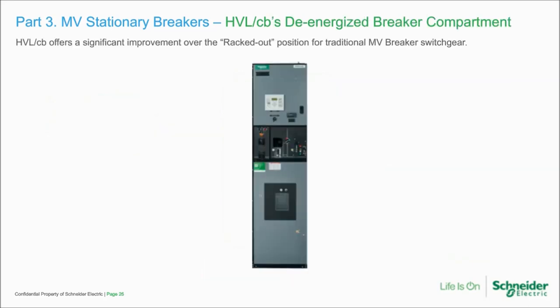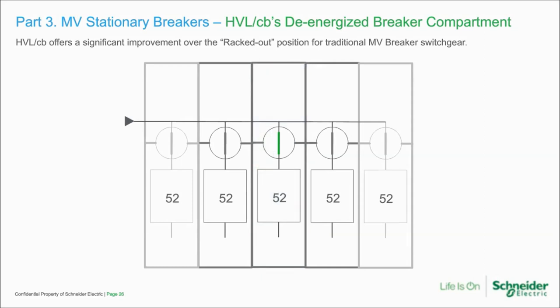This is a great improvement over the racked out position of traditional MV breaker switchgear. Here's a lineup of HVLCB feeders — 52 is the ANSI designation for the breaker, and above you'll see the disconnect as part of the compartmentalization. When the disconnect moves into the open position, the entire breaking compartment is de-energized. This is totally different from the way that maintenance is performed in metal clad withdrawal breaker switchgear.